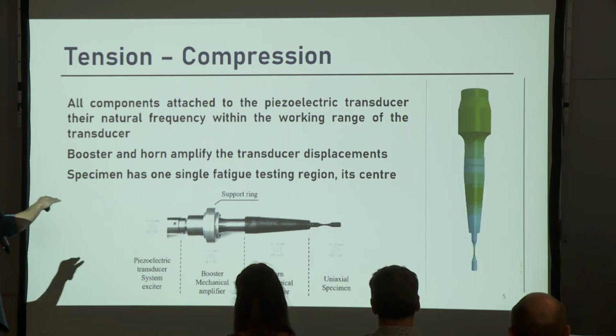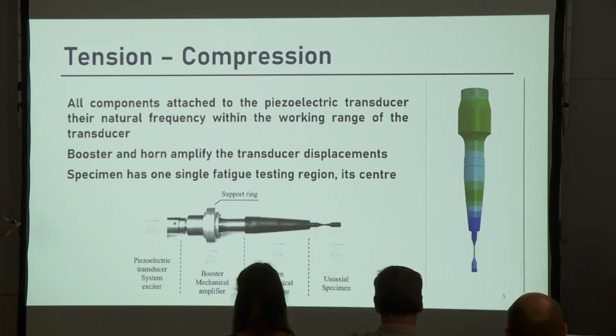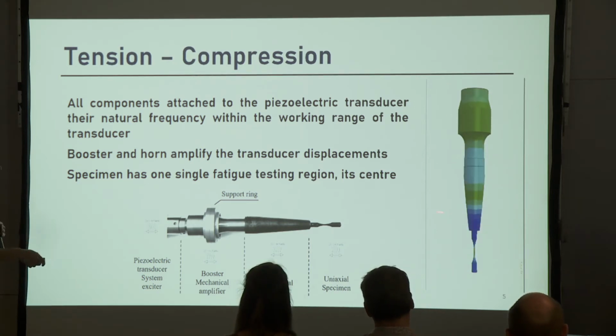In the case of tension compression, we use longitudinal mode shapes with one displacement node in every single component. You can see, like in the greens, where there is almost no displacement. This is where the support ring is placed, and this is where there's no displacement of the specimen, and where the stresses are highest. This is the fatigue testing region.